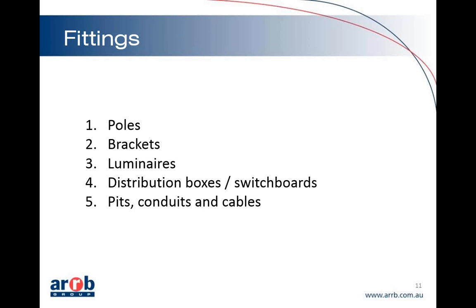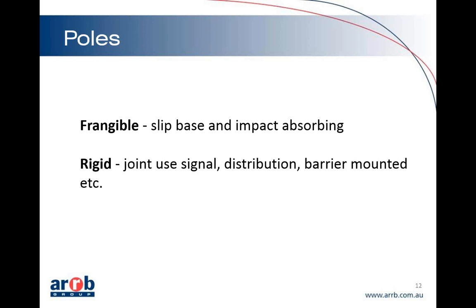Talking about some of the fittings that we use on a public lighting job: there's poles, brackets, luminaires, distribution boxes, and then all the underground stuff. If we were going to split poles into a couple of categories, you're most likely going to split them up and say there's frangible poles — that are impact absorbing — and then rigid poles. I've listed a couple of the types of rigid poles: joint use signal poles, power poles that you might mount lights on, and poles that are mounted on concrete barriers. Normally you try and use as many frangible poles as possible on a job. Sometimes you have to use rigid poles, or it's more beneficial to use a rigid pole if you can combine a public lighting pole and a traffic signal pole.